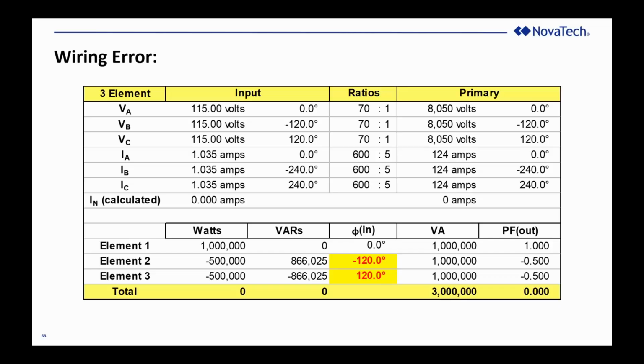This is what happens. The flipped phases have half and in the opposite direction of the correct phase, and it adds to 0. If you have your voltage and your current connected, showing the right value, and your watts and your VARs both look almost 0, that's a dead giveaway that somehow you flipped two PT connections to the meter.